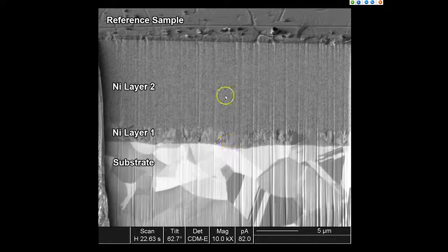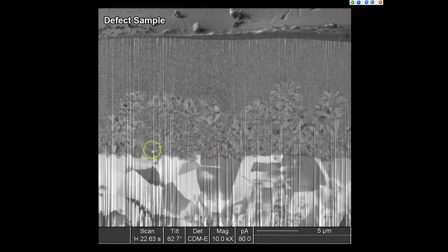And in the SEM, these would look very similar because you don't see grain structure very clearly in the scanning electron microscope. So therefore, the FIB grain structure contrast is greatly improved over what you'd see in the SEM. And so when we go look at a defect region where you could see some waviness on the surface of the sample, you see that that lower layer nucleated in a very bizarre fashion to provide this large nodule of the coarse-grained material before it was overplated with the fine-grained material.